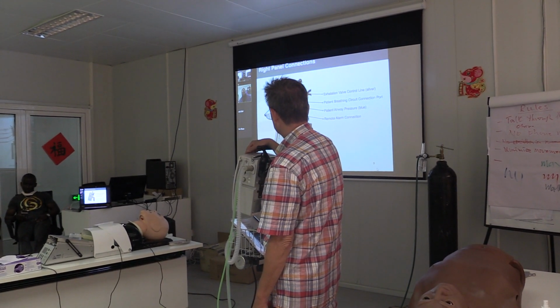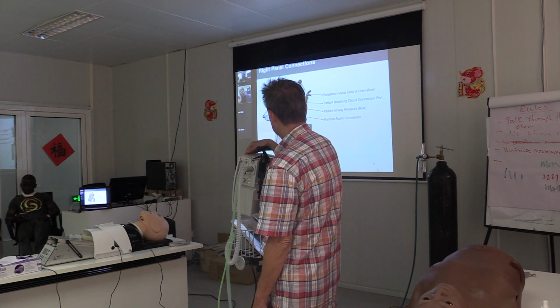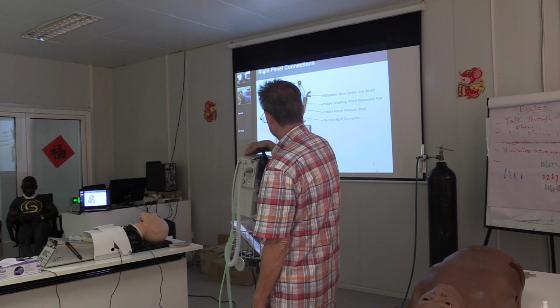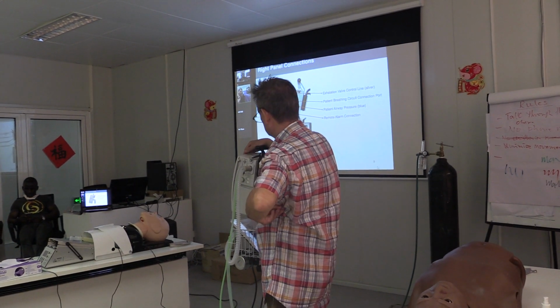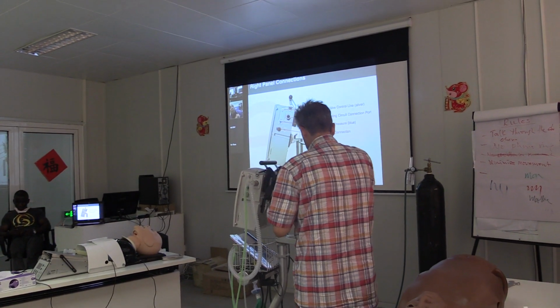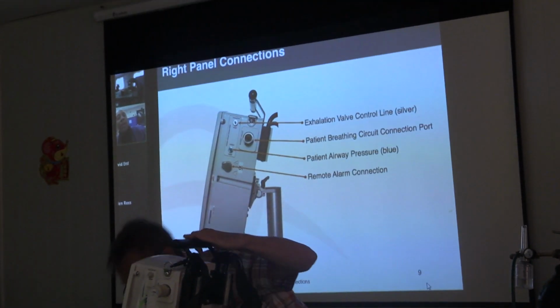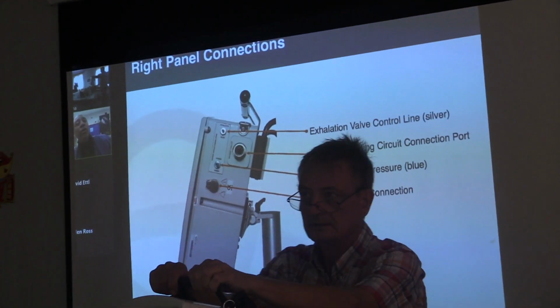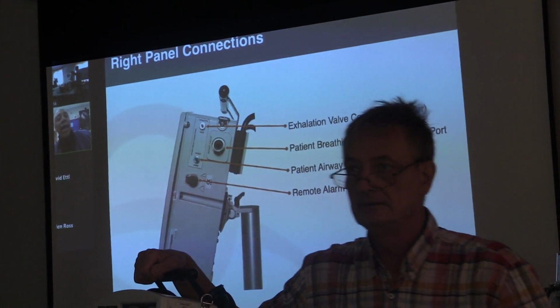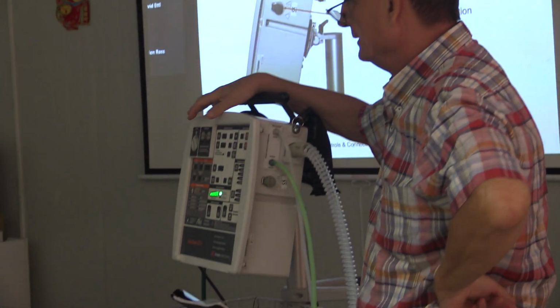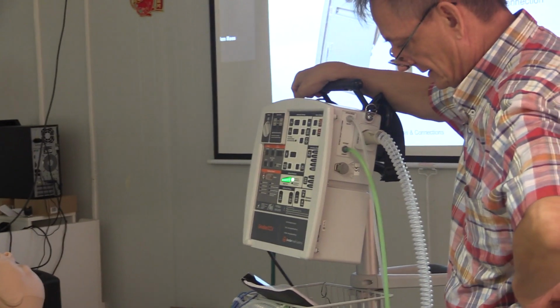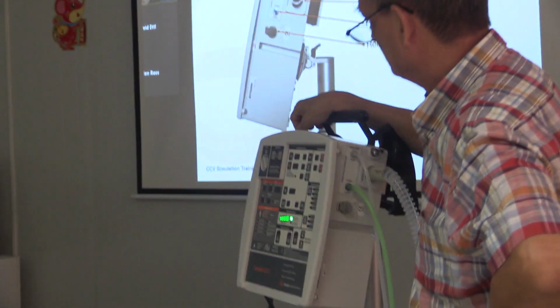you need to be able to connect it. When you're connecting and disconnecting, you have a very special reusable tubing that can be washed and reused. So you want to be able to reuse it as many times as possible. So if you abuse it, if you just pull it any kind of how, and you don't take care to remove it carefully, you will tear the tubing and it won't last. And then you have to worry about getting more tubing. So just be very gentle when you're disconnecting that tubing.